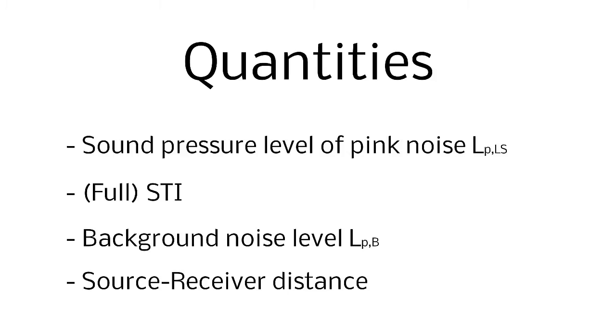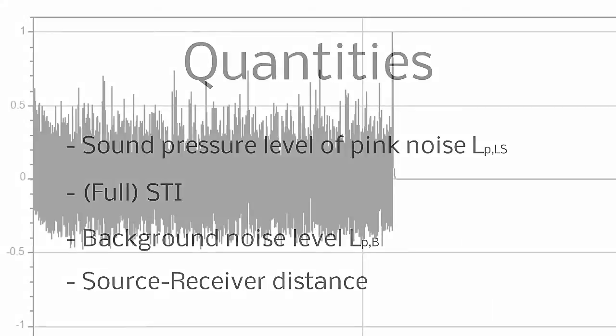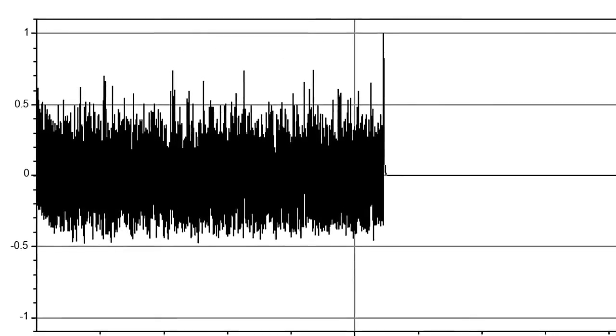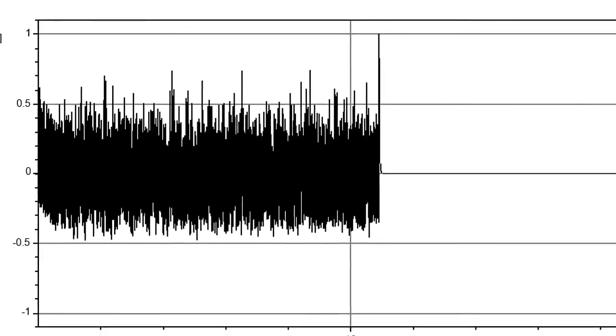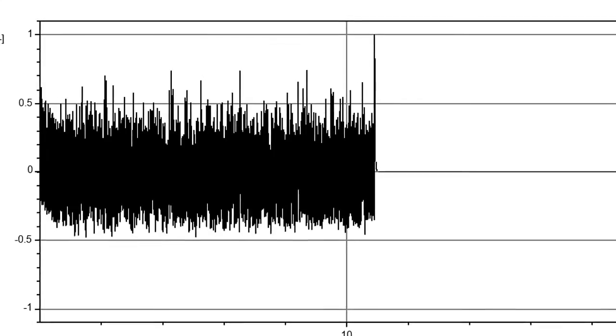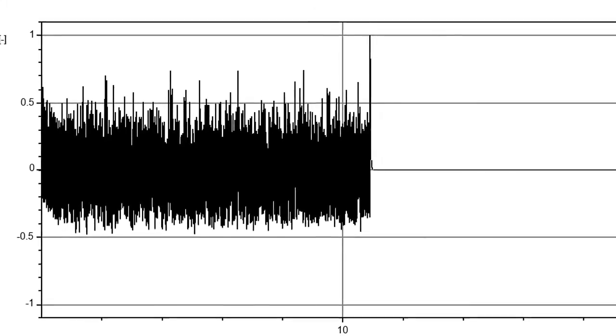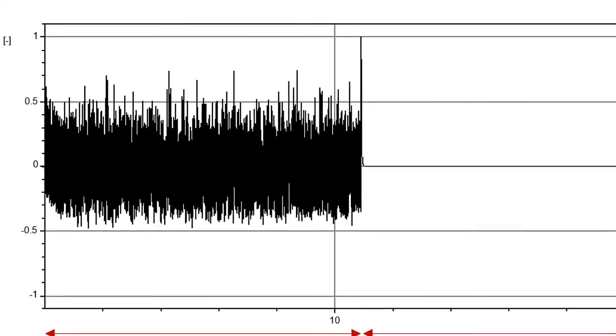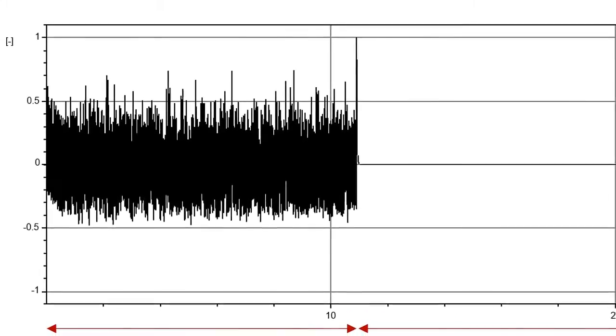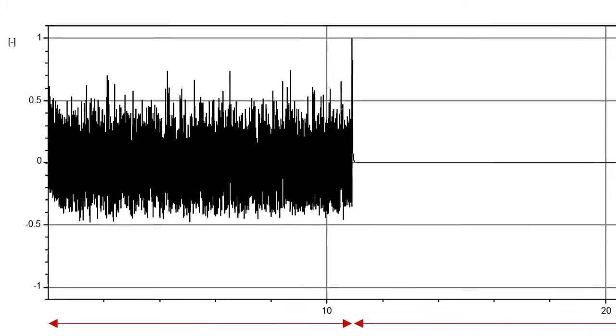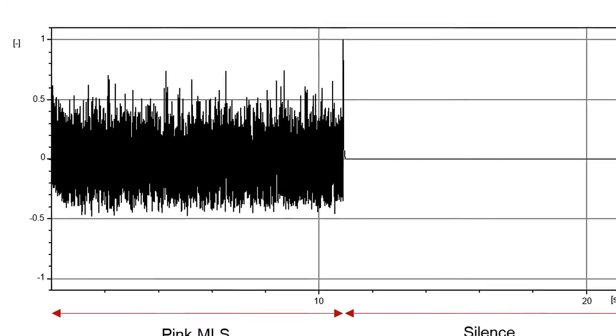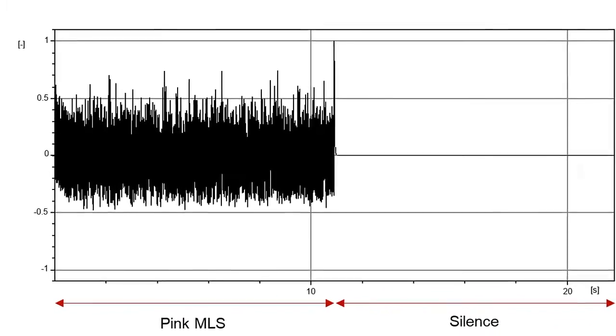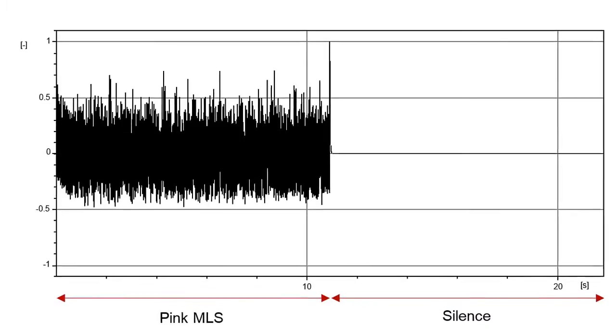In Dirac 6, these four quantities can be measured simultaneously using an intermittent stimulus. For ISO 3382 Part 3 measurements, this is a 10 second pink MLS or e-sweep followed by a 10 second silence to capture the background noise.